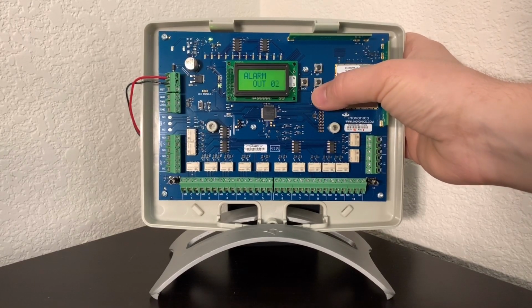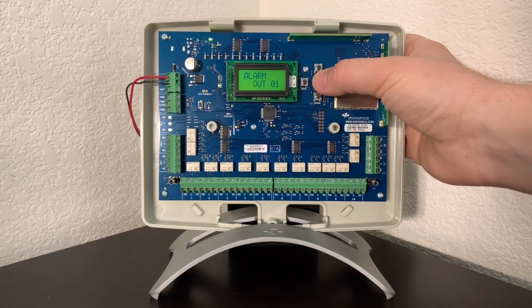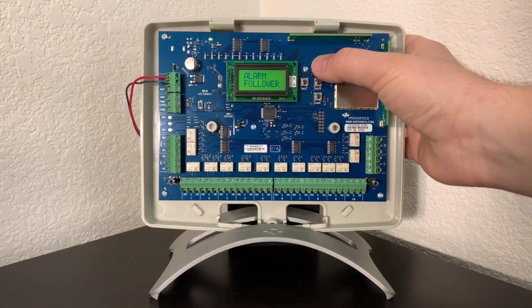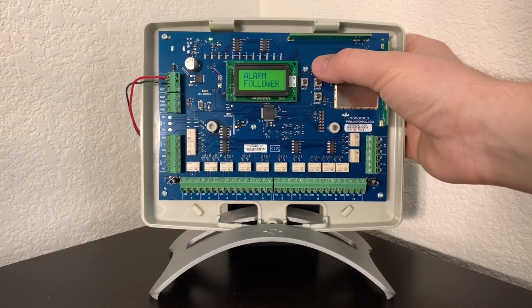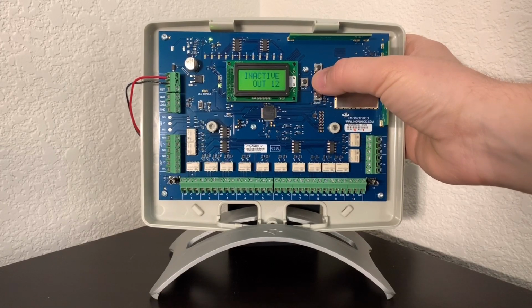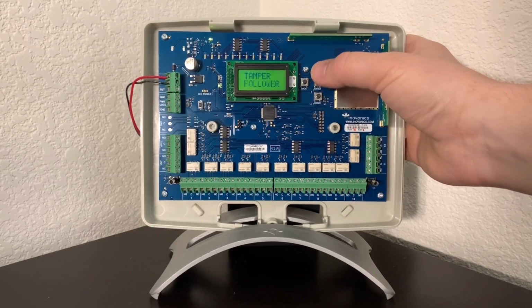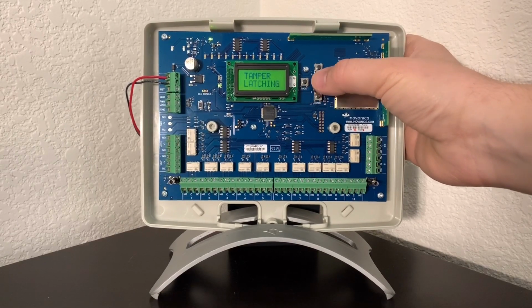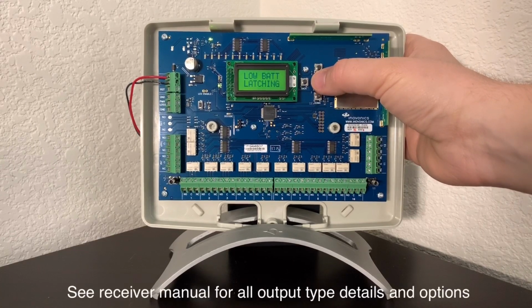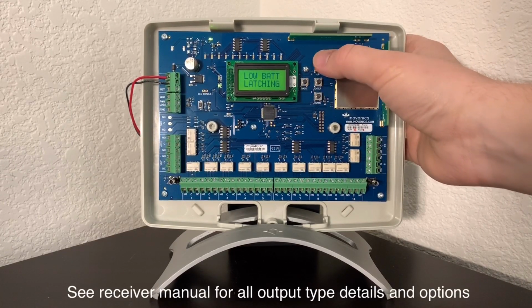And now we'll choose our relay output. I'm going to select Relay 1. And then we can choose our output type of follow, moment, toggle, or latch. We can now select how our trouble conditions report. By default, inactives report to relay 12, tampers report to relay 11, and low batteries report to relay 12. You can change this to whichever you prefer, and then you can select your output type of follow, moment, toggle, or latching.